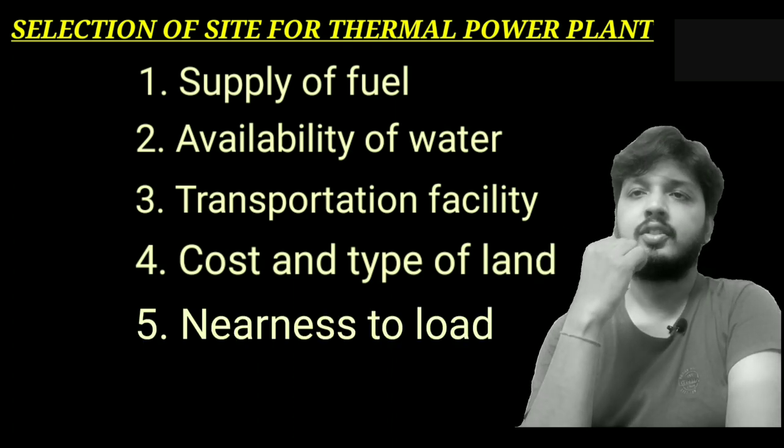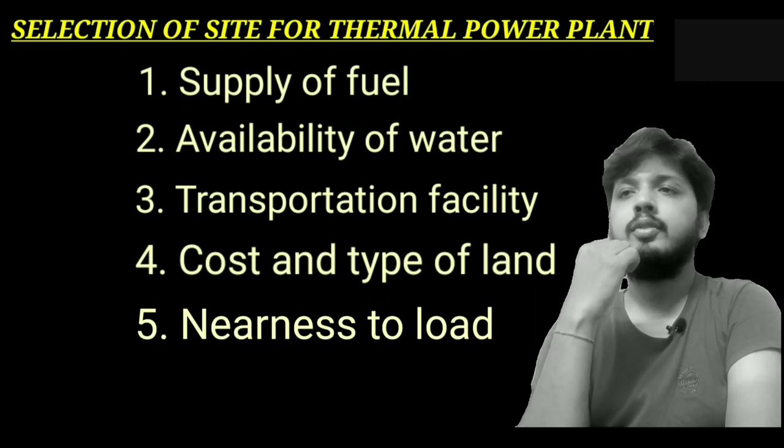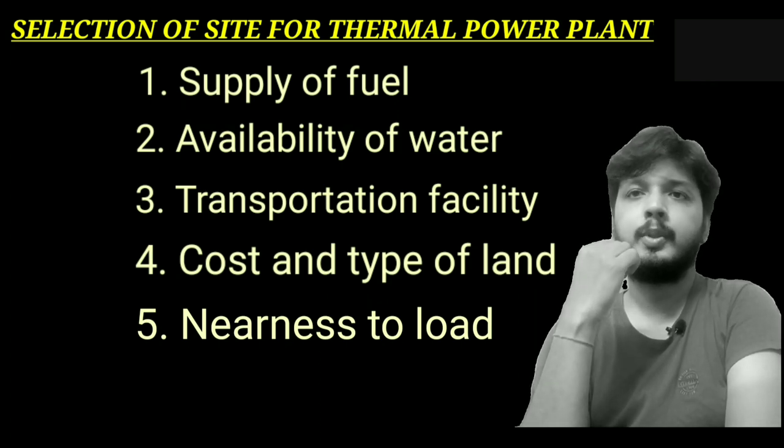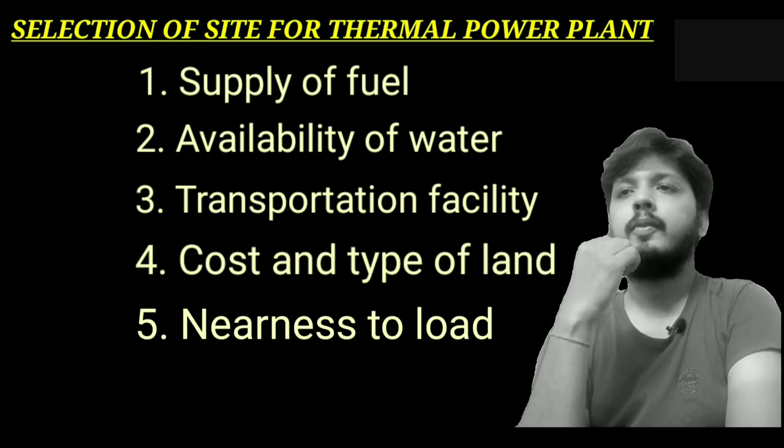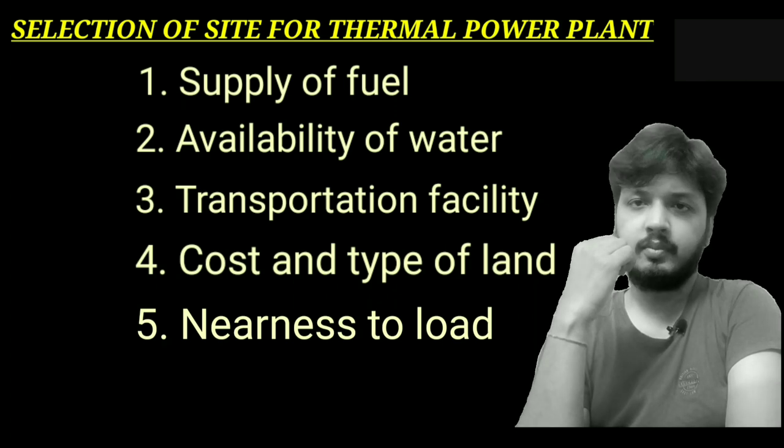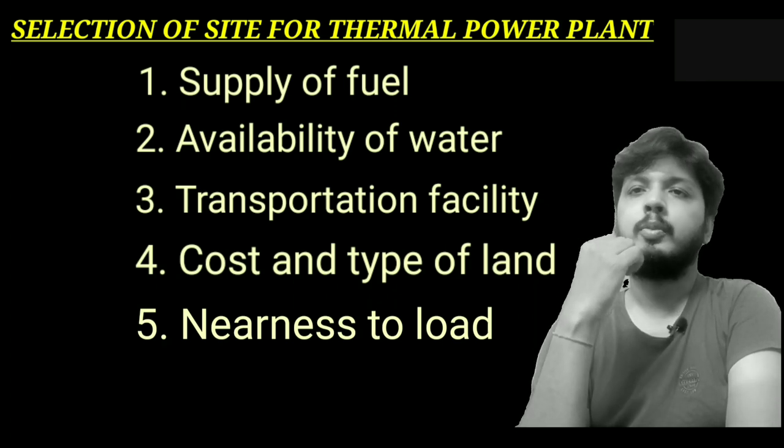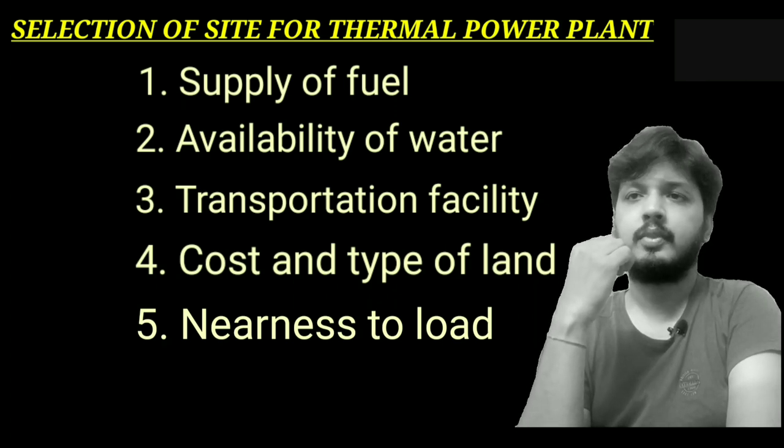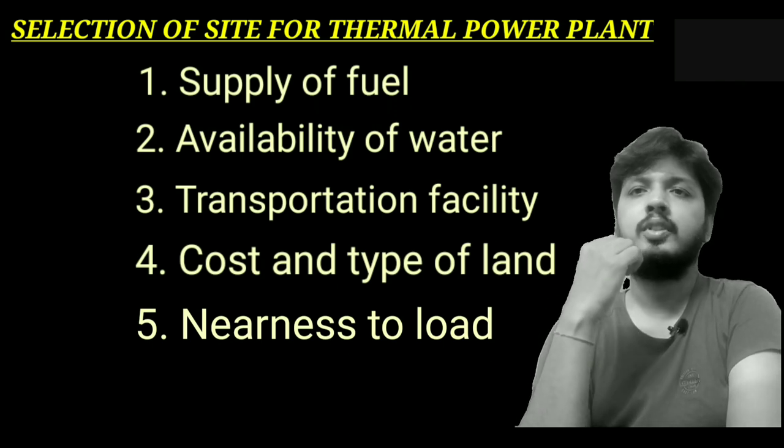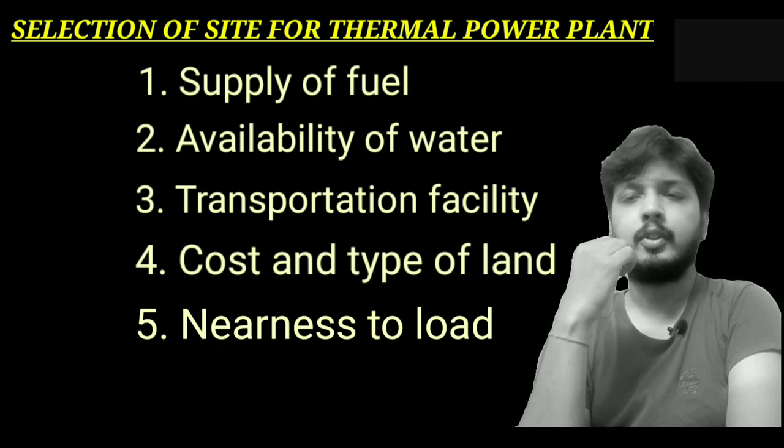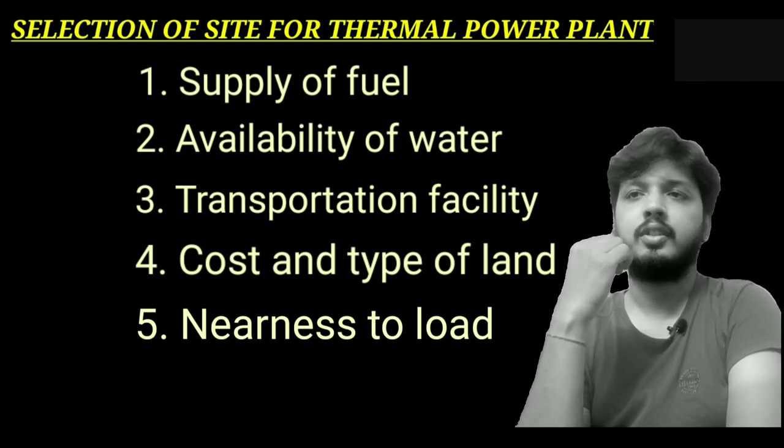Next point is nearness to the load. In order to reduce transmission cost, the plant should be located near the center of the load. This is particularly important for DC systems. However, if AC is the transmission system, then transmission will happen at high voltage, consequently reducing the transmission cost. Therefore, it is possible to install a plant away from the load center provided other conditions are favorable for AC.